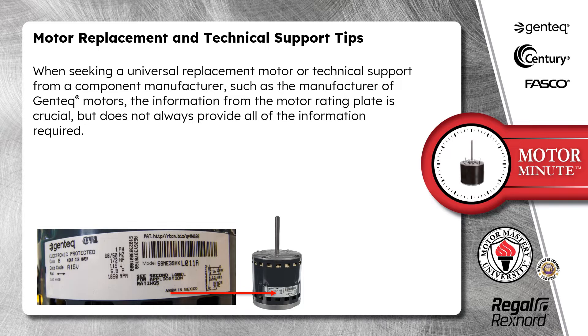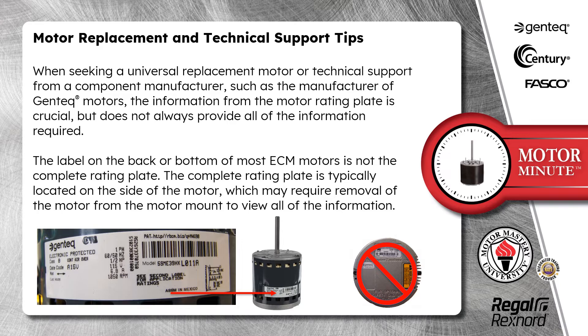When seeking a universal replacement motor or technical support from a component manufacturer, such as the manufacturer of Genteq motors, the information from the motor rating plate is crucial, but does not always provide all of the information required. The label on the back or bottom of most ECM motors is not the complete rating plate. The complete rating plate is typically located on the side of the motor, which may require removal of the motor from the motor mount to view all of the information.